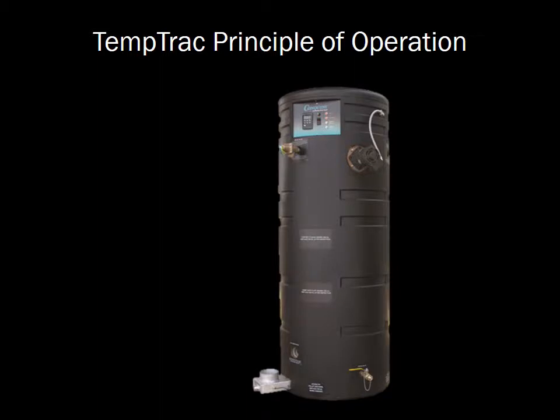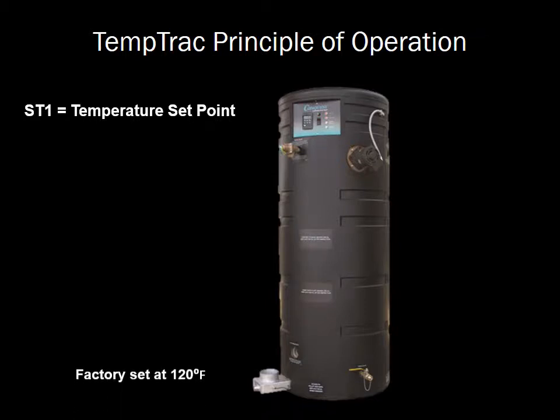The water heater operates to satisfy the stored water temperature set point of the Temptrac operating control. The value of the control set point ST1 is the desired stored water temperature. The unit shipped with a factory set point of 120 degrees. Demand will typically create a drop in stored water temperature, thus activating the call for heat sequence of the water heater temperature control system. There are 3 temperature sensors that control the operation of the CONQUEST water heater.